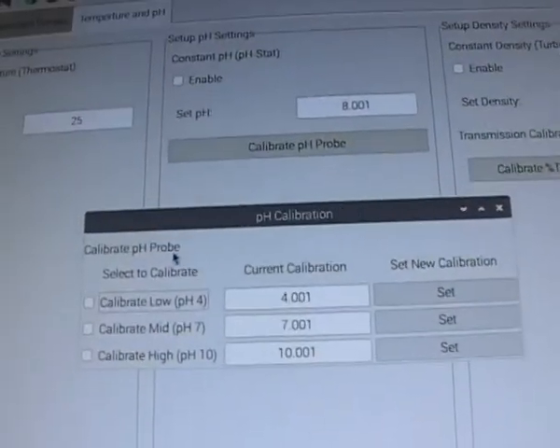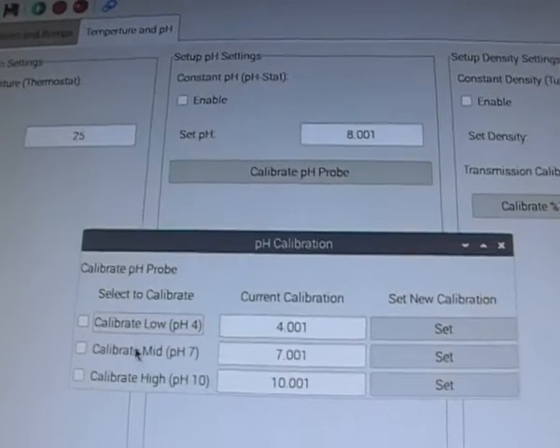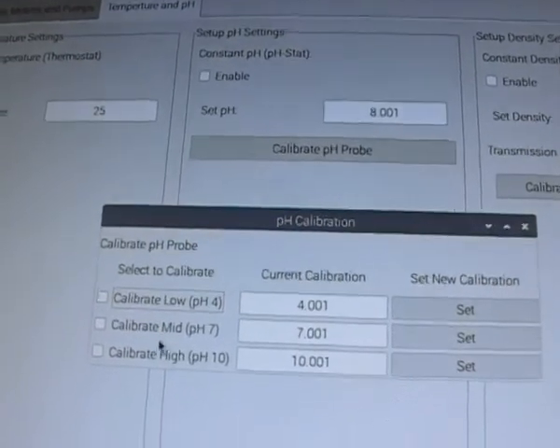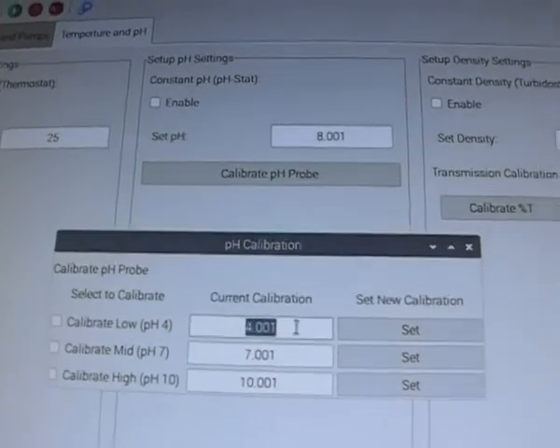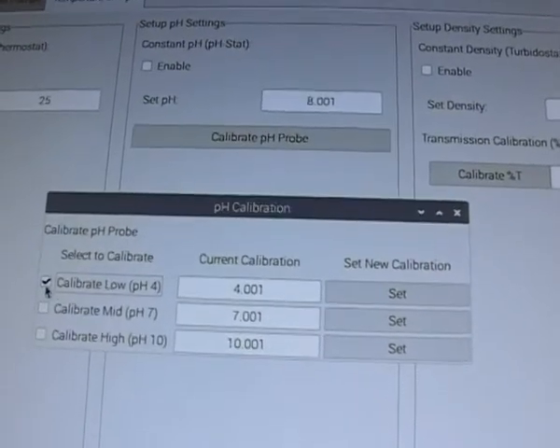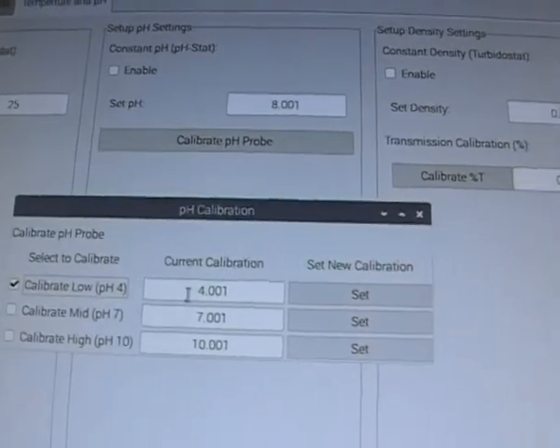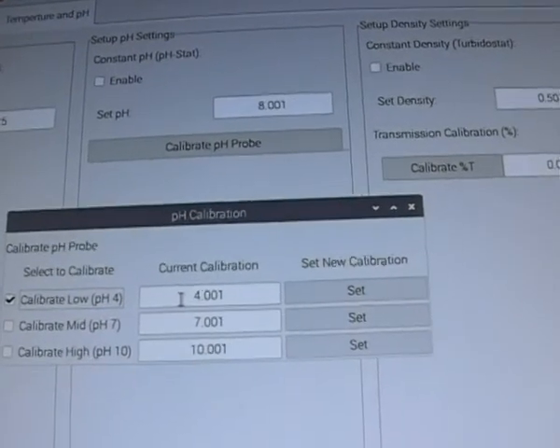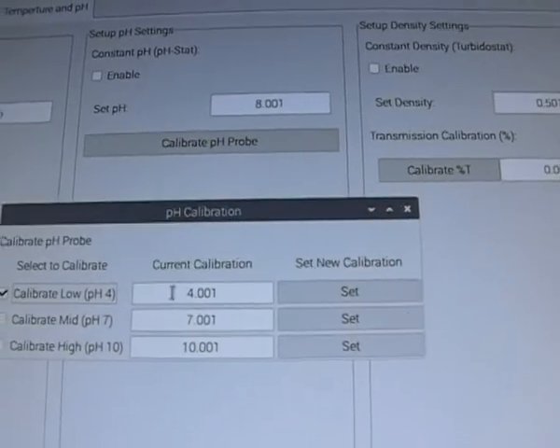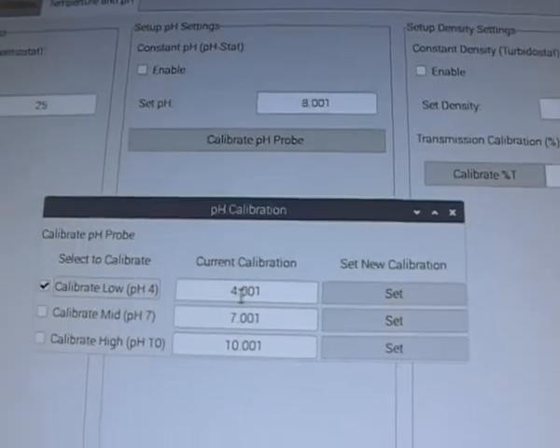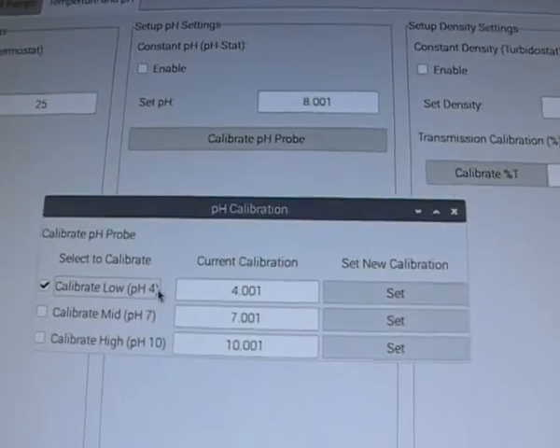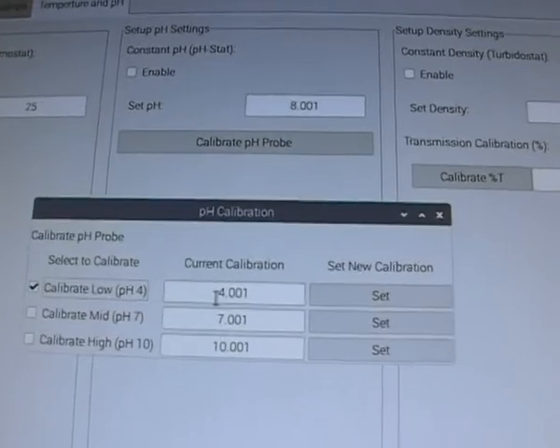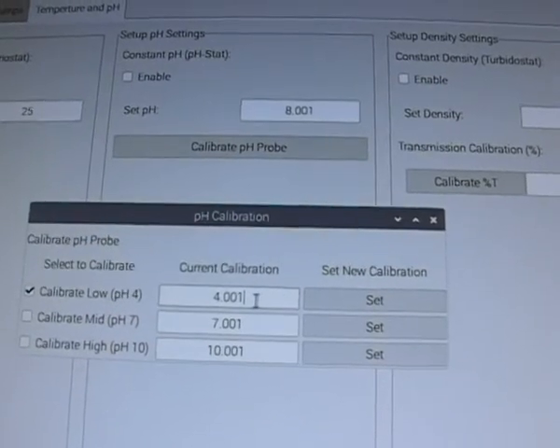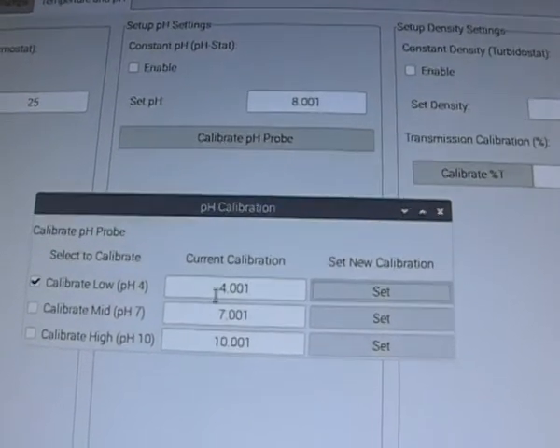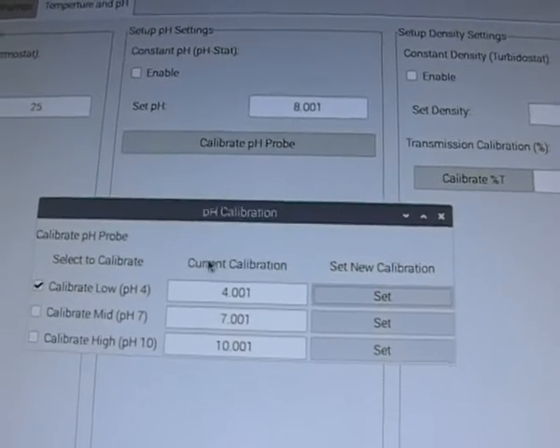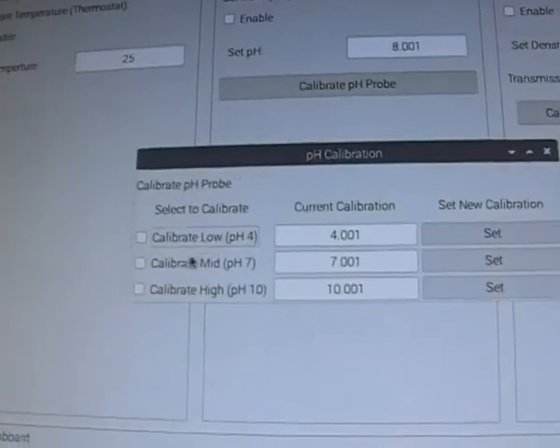That just works by selecting the calibration. We have a 3-point calibration: 4, 7 and 10. Once you click that, you select that you want to calibrate the low point, and the pH probe enters its calibration procedure. It'll display what the current calibration value is, so you put the pH probe into a pH 4 solution, and once it gets to a stable value, you just click set, and that'll all update in the software, so you don't have to worry about that. And you just continue that for each one of the calibration settings.